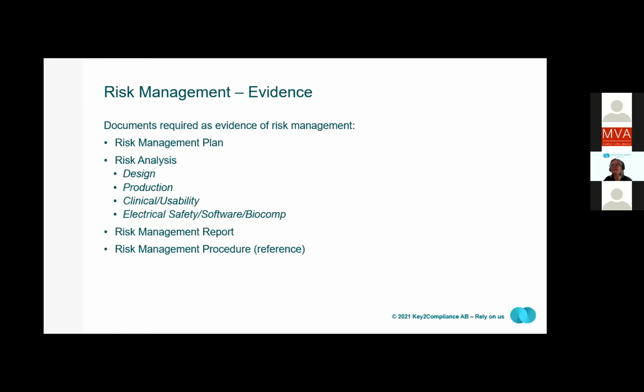As evidence that you comply with the risk management GSPRs, you would need to include the risk management plan, the risk analysis, the risk management report, and also the risk management procedure, or a reference to that procedure, since it is a QMS document, not directly part of the technical documentation, but there is information that would be relevant to the notified body TD assessment of the risk management section. So the risk analysis itself should also contain the analysis from different parts, such as design, production, clinical, usability, and other areas such as electrical safety, biocompatibility, and software, depending on the device.